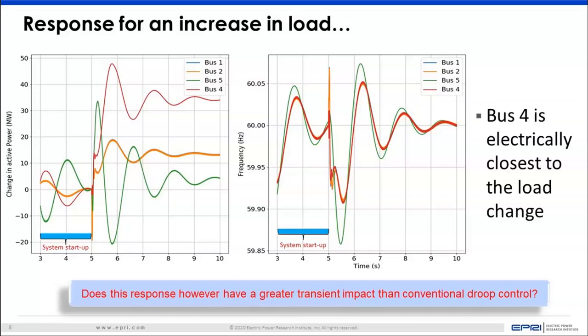But what this shows us is that when you have an increase in load in this setup, because of having that kind of constant frequency control, within a few seconds your control is able to bring frequency back to 60 hertz, which is very different from what we know as droop control, where it takes a lot of time for droop control and secondary frequency response to bring this back up to 60 hertz. But then one asks the question, how much additional energy is required in this perspective?